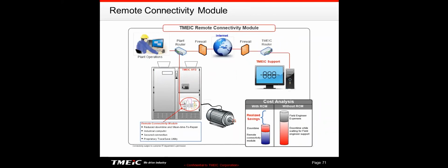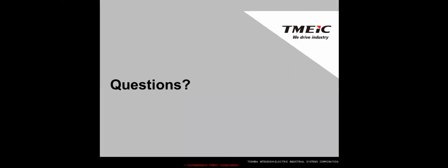Now, this is a remote connectivity module, something that comes with the TMEIC drives. It is a separate standalone controller that doesn't do anything to control the drive. It's kind of a little watchdog, or a supervisor that sits outside the drive and just watches what the drive is doing. Because it cannot control the drive in any way, we don't have problems with cyber crime on this because it is isolated from the drive control system, but it's an excellent way for you to see what's going on with the drive in a very cyber-safe manner. And if the drive were to blow up and the control board in the drive were to fail, this still has all the data so that you can go in and download that and look at it.